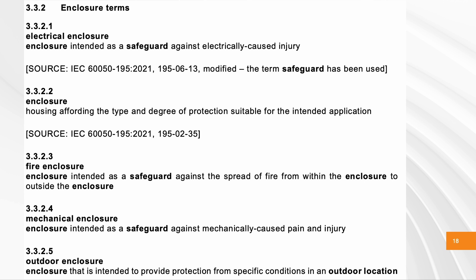One safeguard can be used against several kinds of energy. For example, an enclosure — think of the housing or casing of a product. It might serve as an electrical safeguard against electrical shock. It can also function as a fire enclosure to contain fire inside the product and prevent it from spreading outside. It can also act as a mechanical safeguard — for example, to make sure rotating parts don't catch someone's hair or clothing.